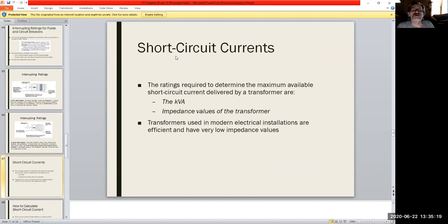So another topic that I look at is what short circuit currents are. Well, go with the definitions, right? A rating is required to determine the maximum available short circuit current delivered by a transformer, or kVA, right? VA being our apparent power and our capability. And notice it's in the K, so this is big stuff. And the impedance values of the transformer.